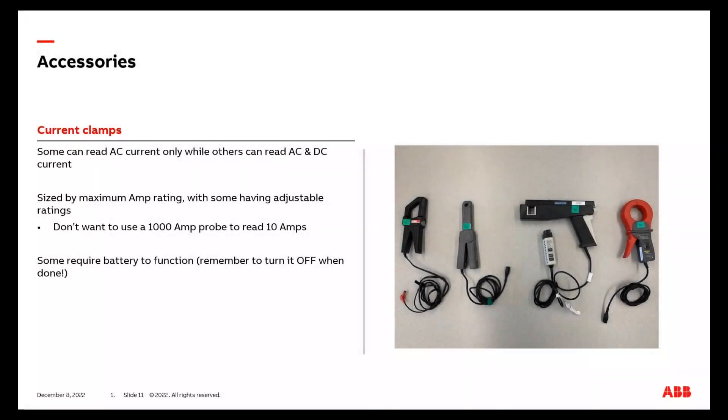The next accessory you'll need to analyze a VFD is a current clamp. Some current clamps can read only AC current, while others can read AC or DC current. Some current clamps require a battery to function, while others do not. If you do have a battery with your current clamp, make sure when done using it to shut it off. Otherwise, when you come back and want to use it again in the future, the battery most likely will be dead. You'll have to go scramble to find a new battery.